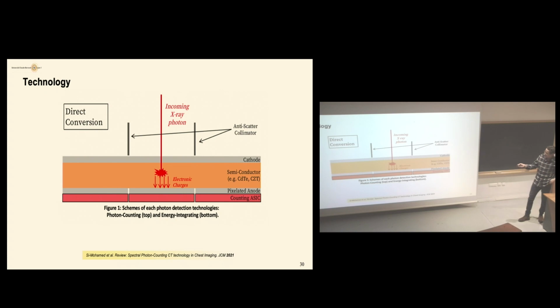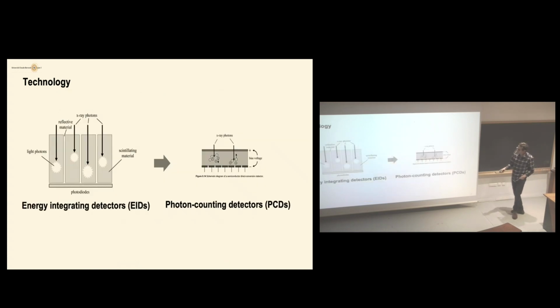Before that, I want to highlight that you no longer have the thin layer around each pixel detector, because you no longer have propagation of visible light, so you don't need to prevent cross-contamination. You can also see that the surface of the pixel detector is much smaller than the energy integrated detectors, for many reasons.